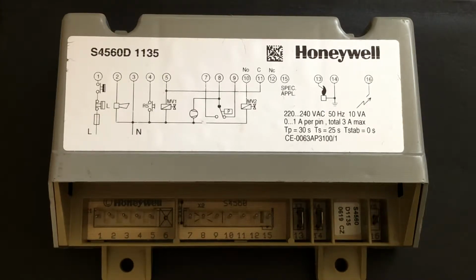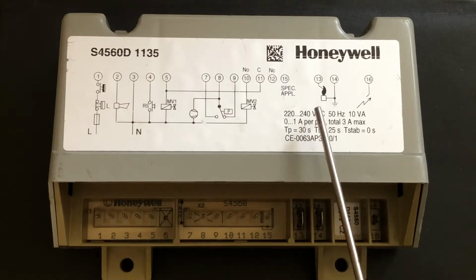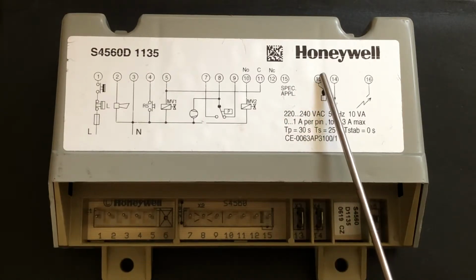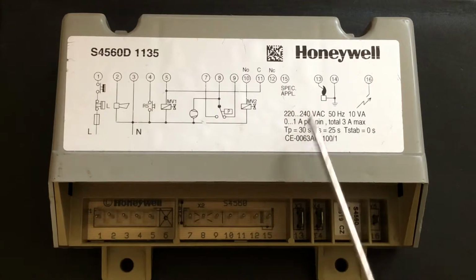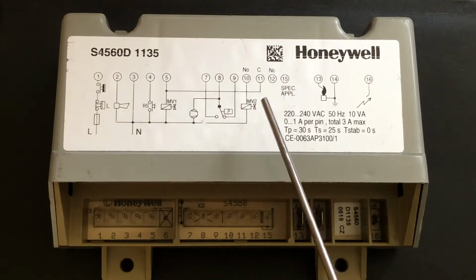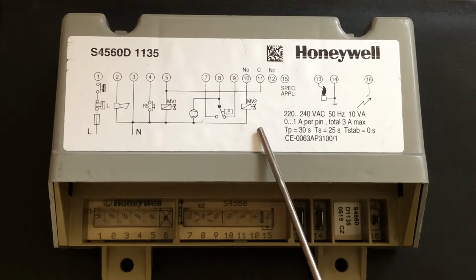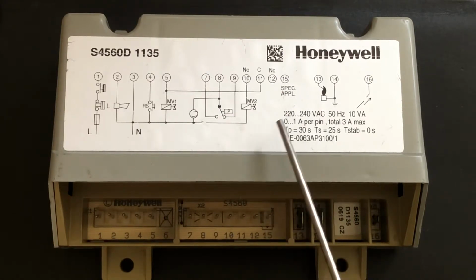Number 5 will be open, and then you will still have power to number 11, which is a common with number 10 and number 12. Now number 10 is normally open, so this common will wait until the ionization probe sends the right signal. As you'll see here, you have the ionization probe, which is number 13. The ionization probe will send a correct signal back into this controller, and then this controller will sense the flame is present, and you'll open the secondary valve, and then the entire burner will run.